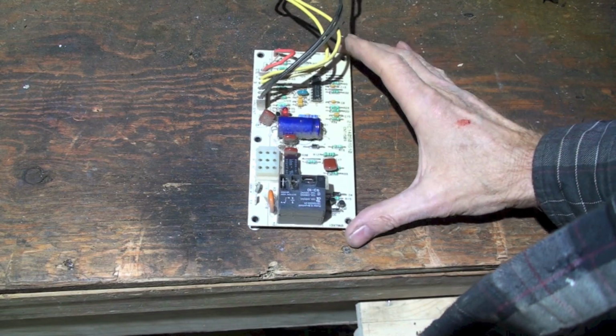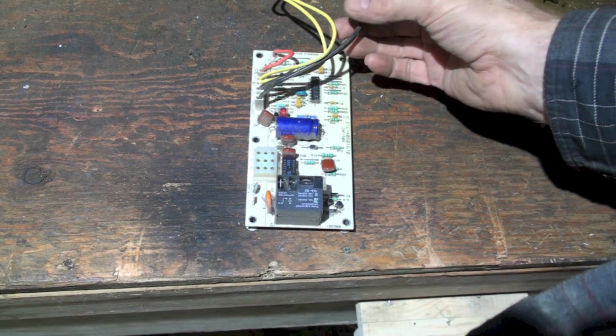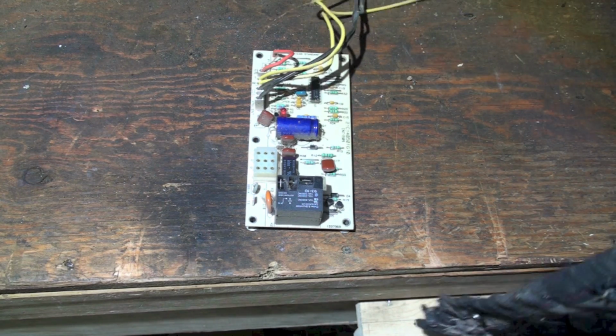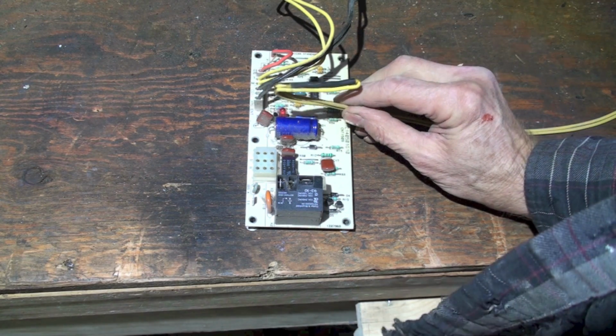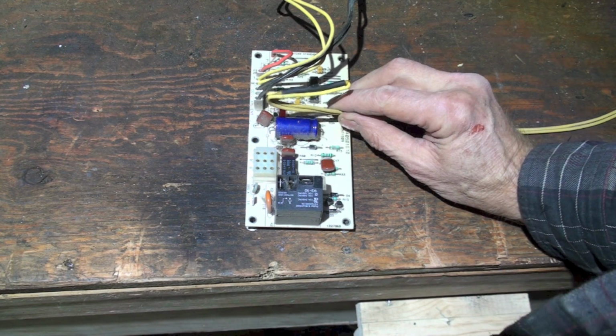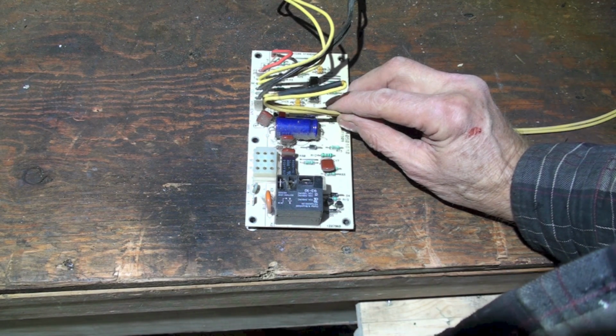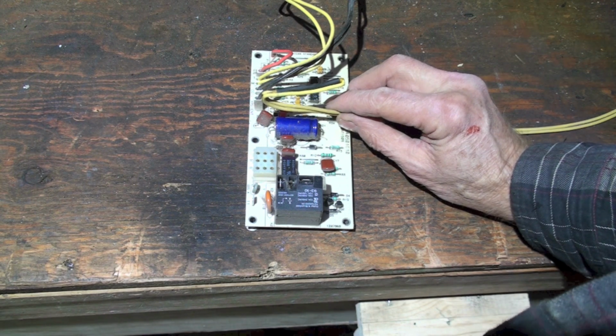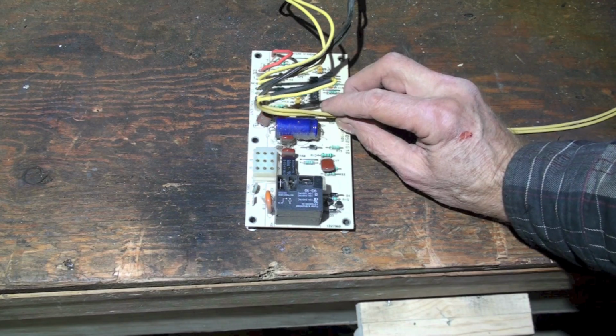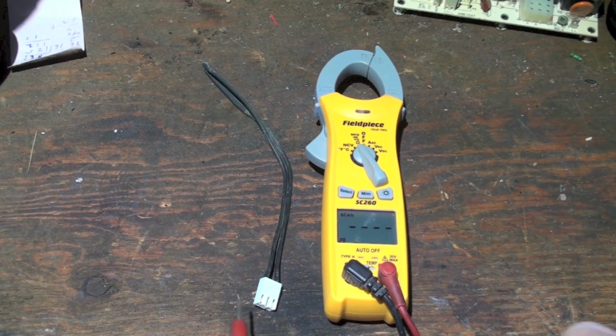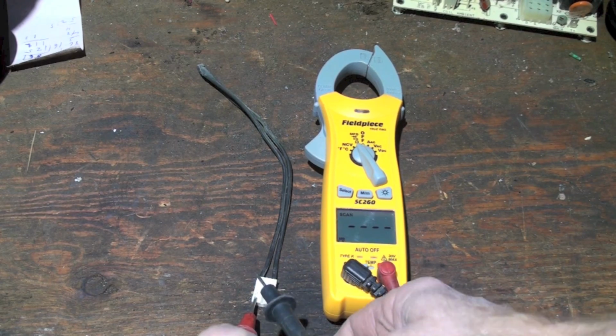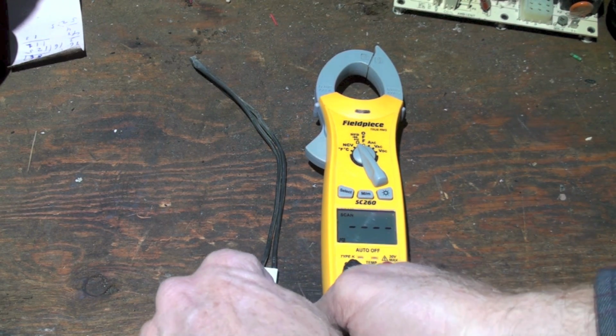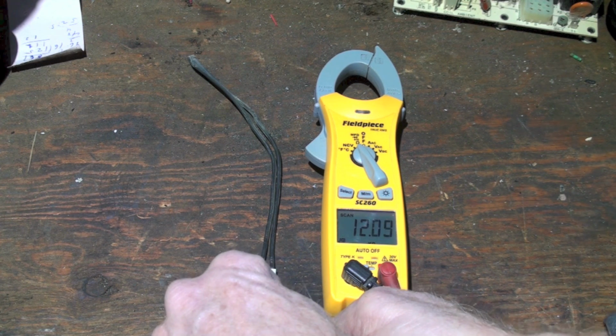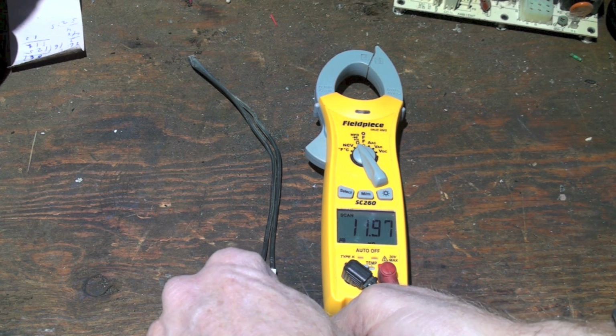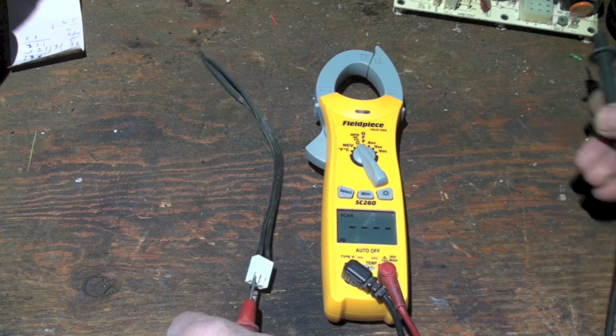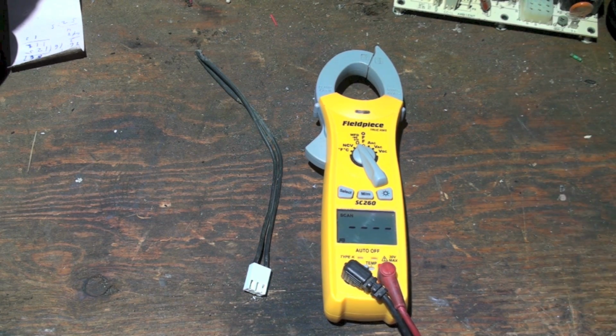Okay, here we've got a little closer look at this thing. What I think is kind of important here is looking at these probes, maybe a little closer view of them. They're just a thermistor placed in the line. Now I'm going to pull both of those probes off, and we can note how the temperature changes with the resistance. Okay, if I take the probes and I go to either side of the temperature probe, I'm going to read 12.09, okay, 12 kiloohms. So that's going to change with temperature.